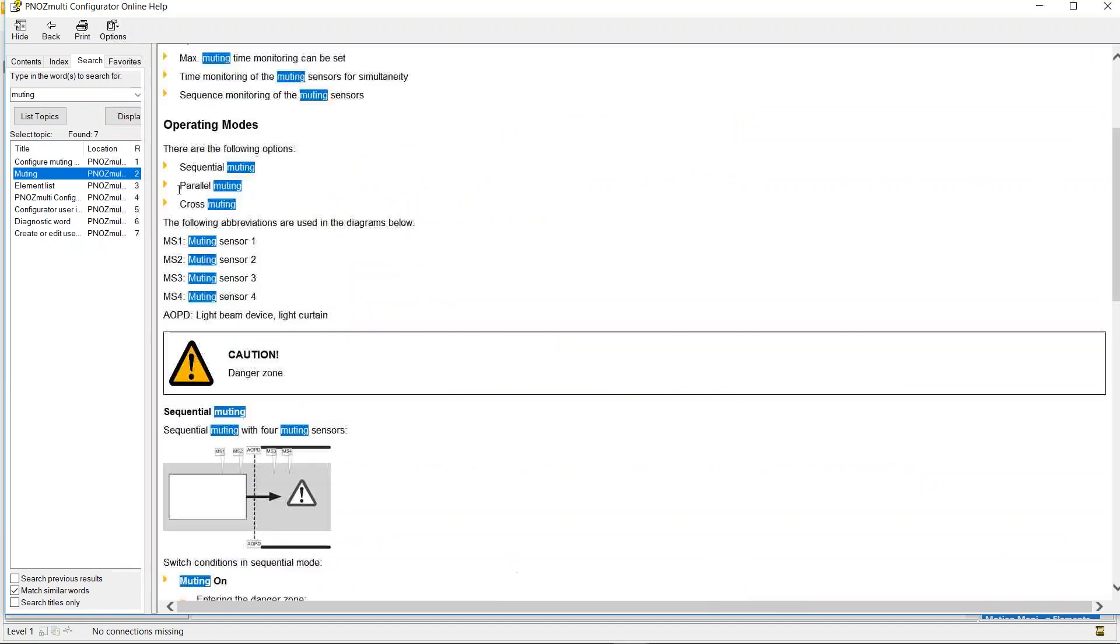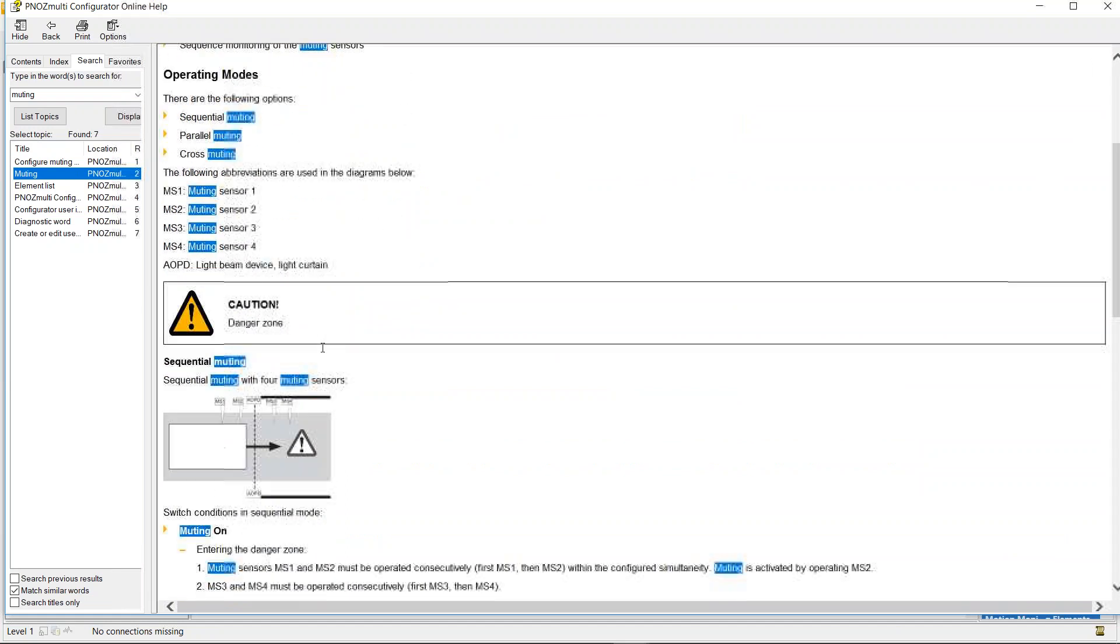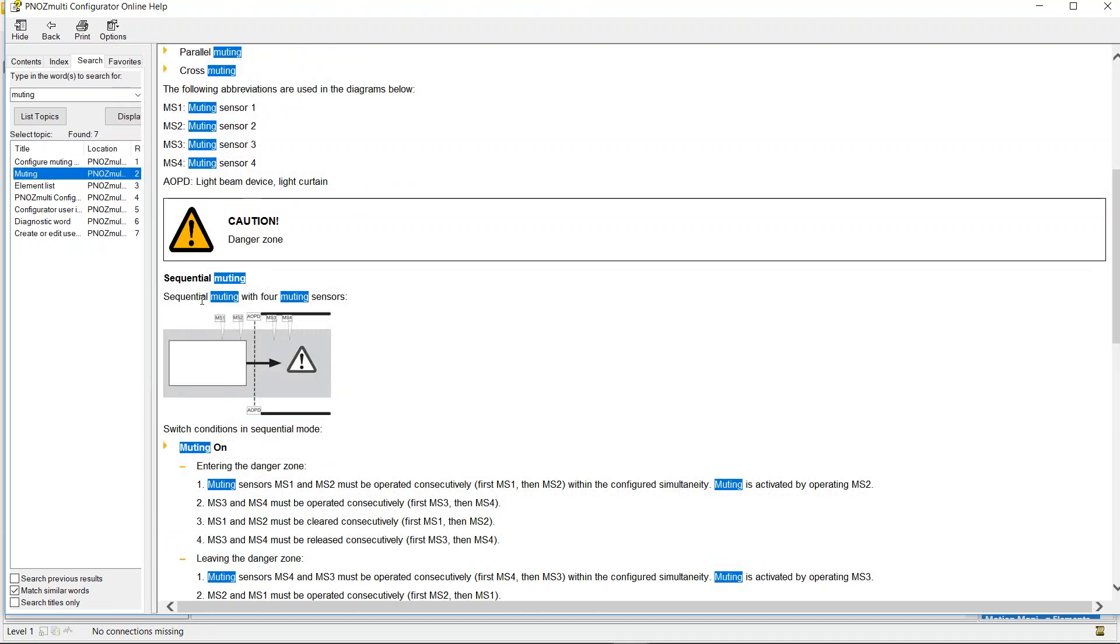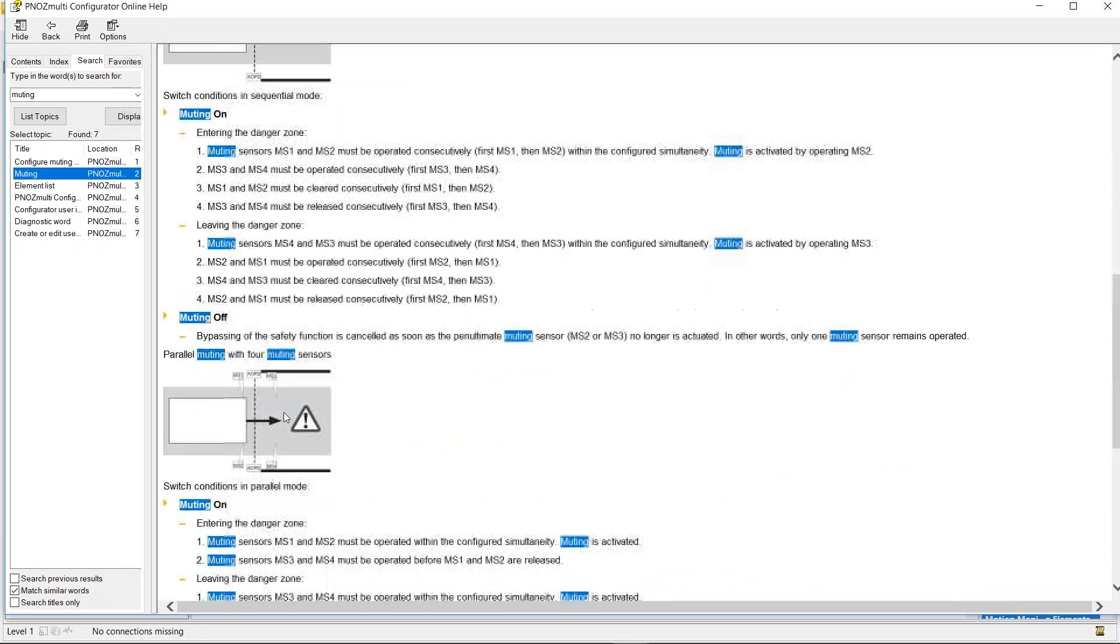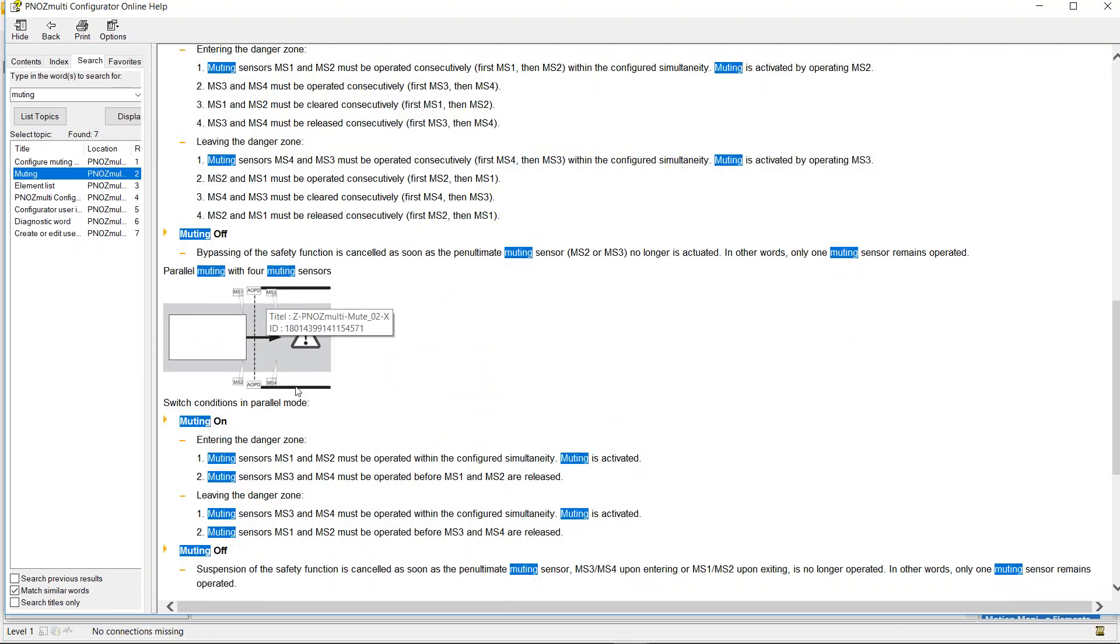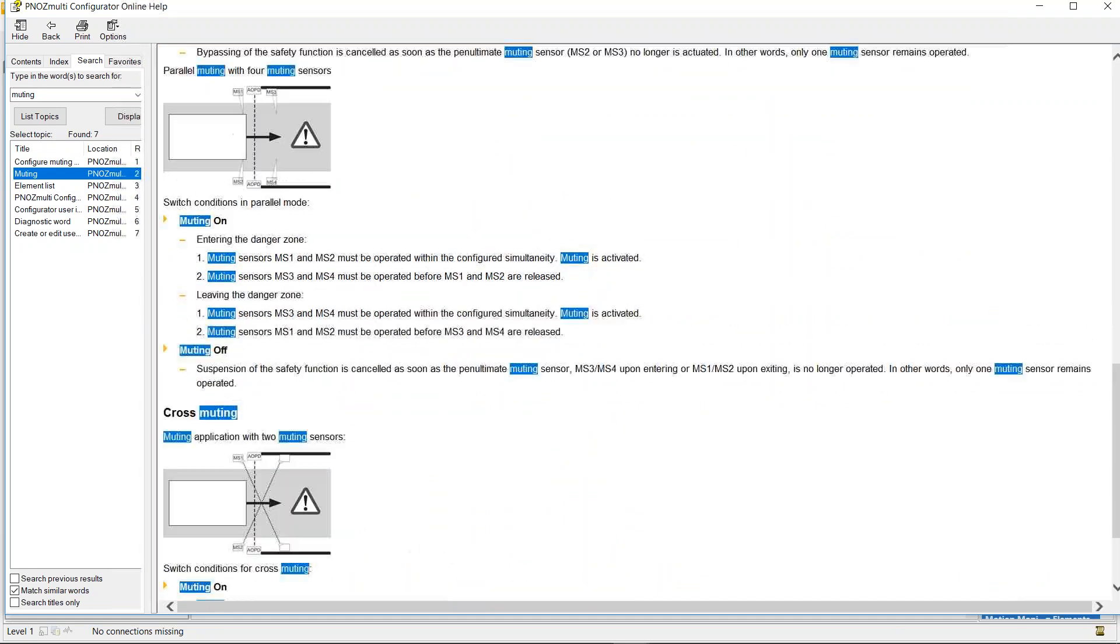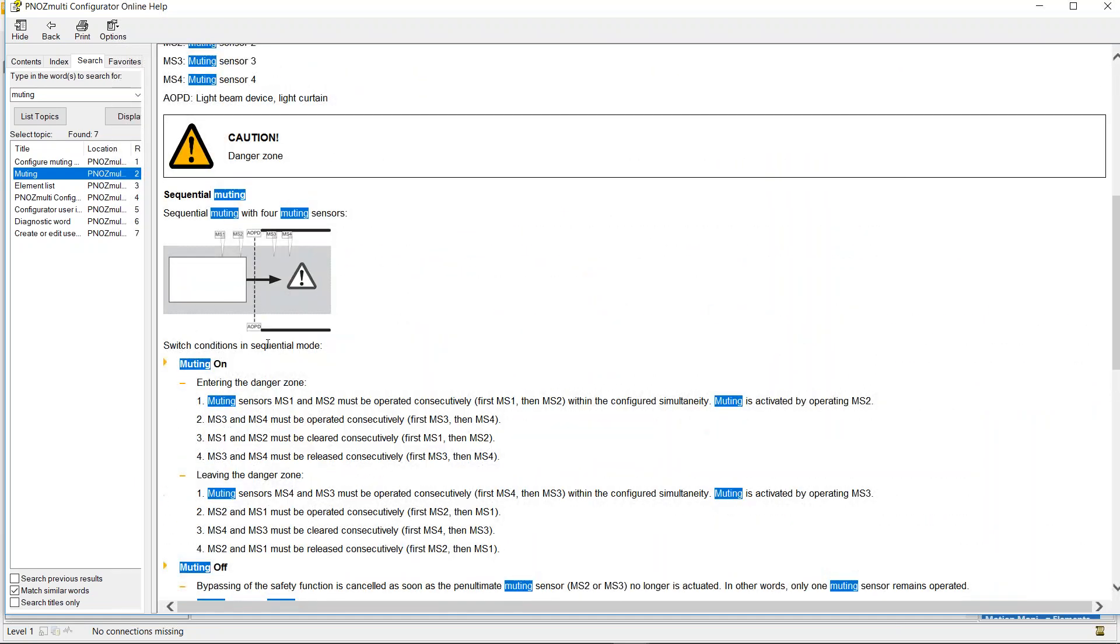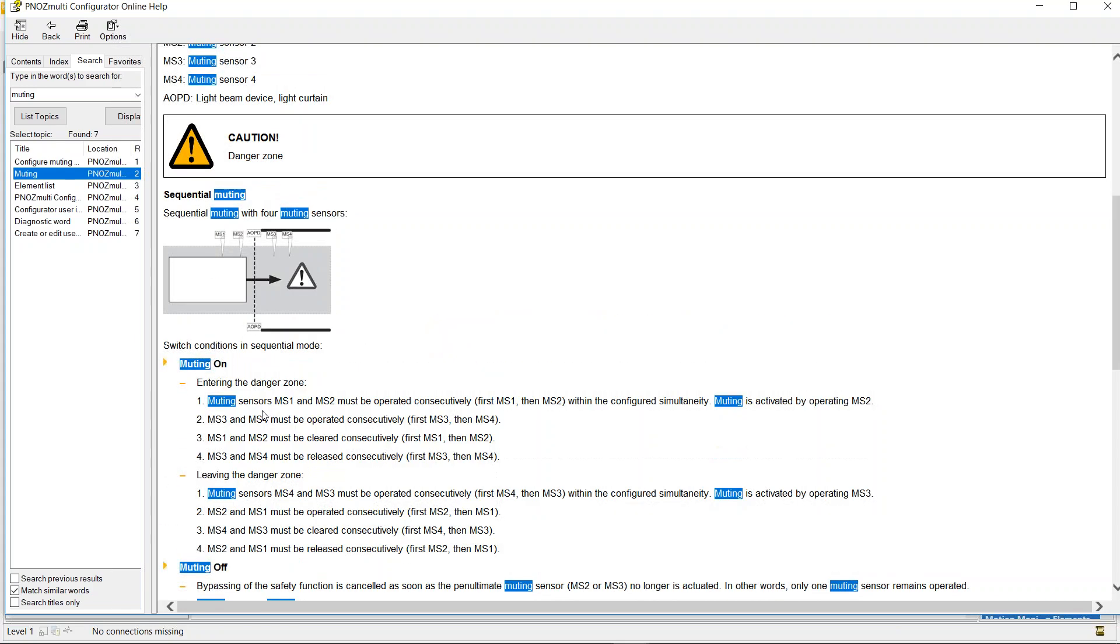These can be found in the help section in the PNOZmulti Configurator under muting. It says there's three types: sequential, parallel and cross, and it gives us a good detail of the application of sequential muting, that your muting sensors one, two, three and four need to be arranged in this orientation with the light curtain here in the middle. And it also gives you the steps that the muting has to take place for it to be healthy. So for muting on it has to be in this order and for muting off it has to be in this order. And it says that in any other order the logic will know that it's a fault and will shut off the output.